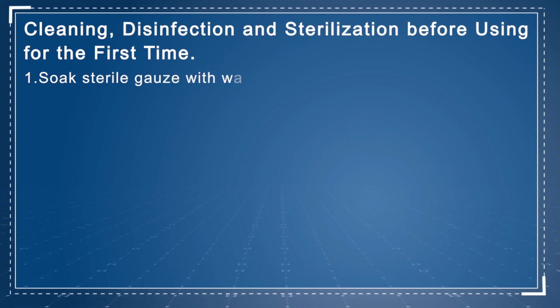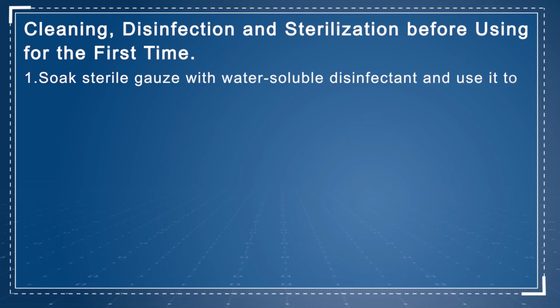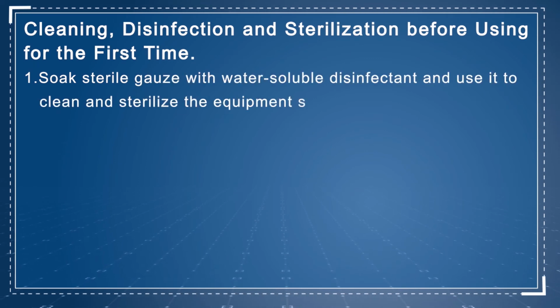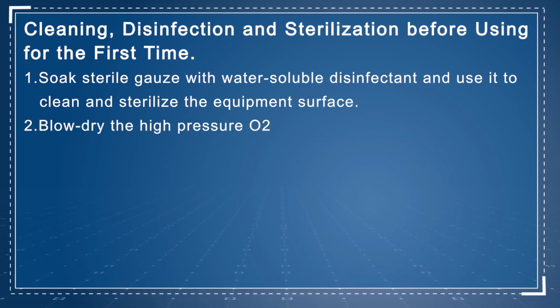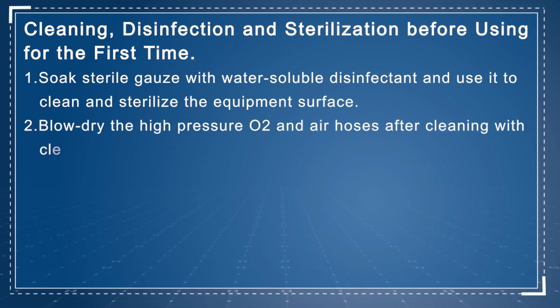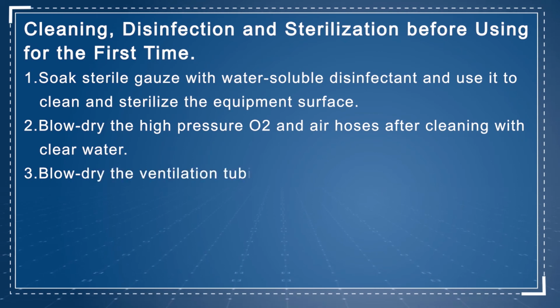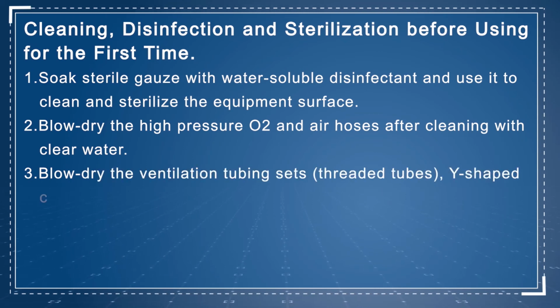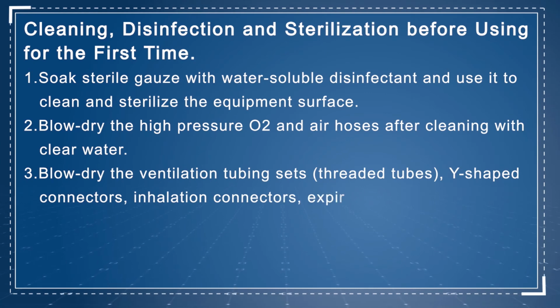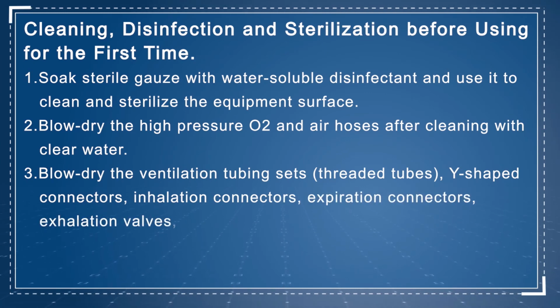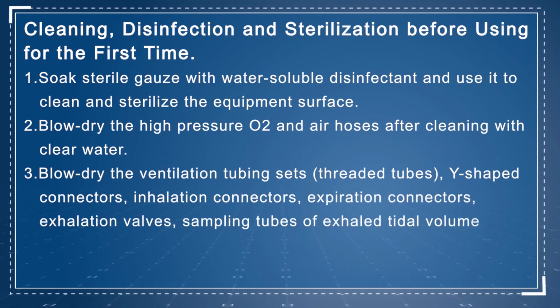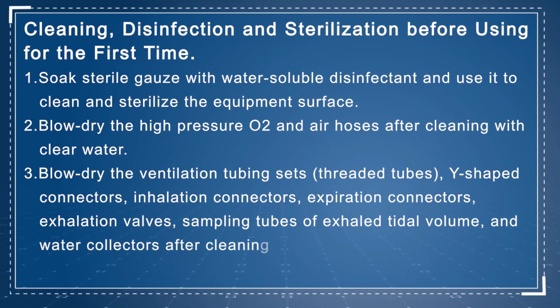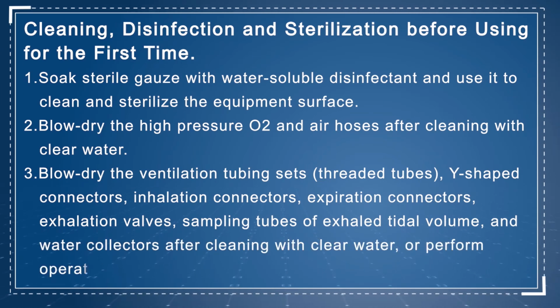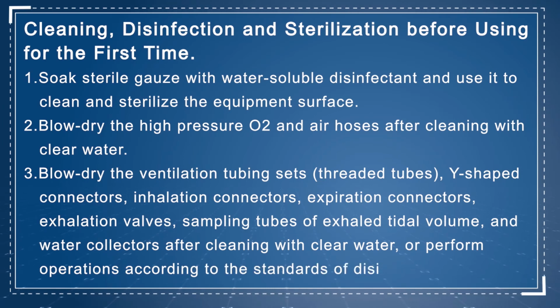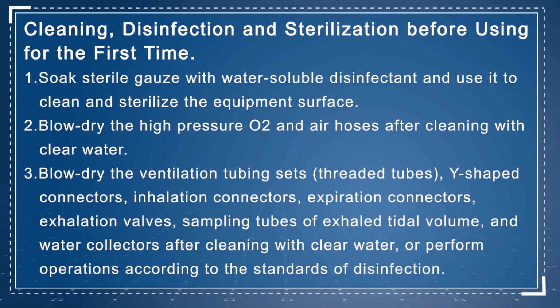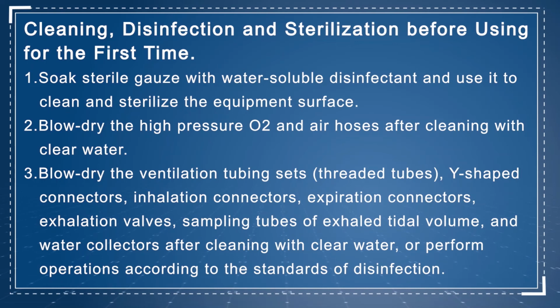1. Soak sterile gauze with water-soluble disinfectant and use it to clean and sterilize the equipment surface. 2. Blow dry the high-pressure O2 and air hoses after cleaning with clear water. 3. Blow dry the ventilation tubing sets, Y-shaped connectors, inhalation connectors, expiration connectors, exhalation valves, sampling tubes of exhaled tidal volume and water collectors after cleaning with clear water, or perform operations according to the standards of disinfection.